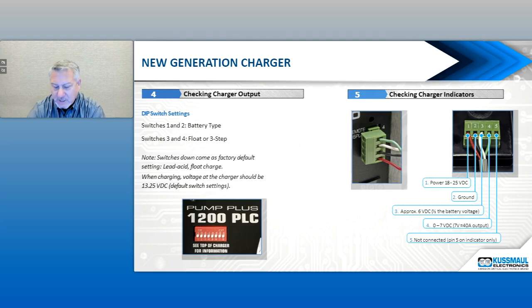You might think you don't want a float charge, but keep in mind these chargers are checking the battery 120 times a second to see what the status is. So even though it says float charge, don't think of that as just a trickle charge. It's checking the battery's state and adjusting its current accordingly.